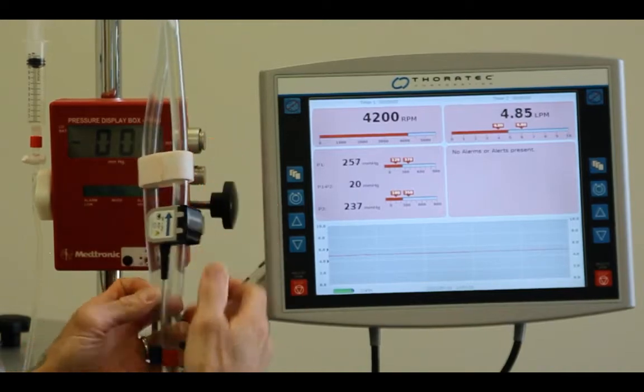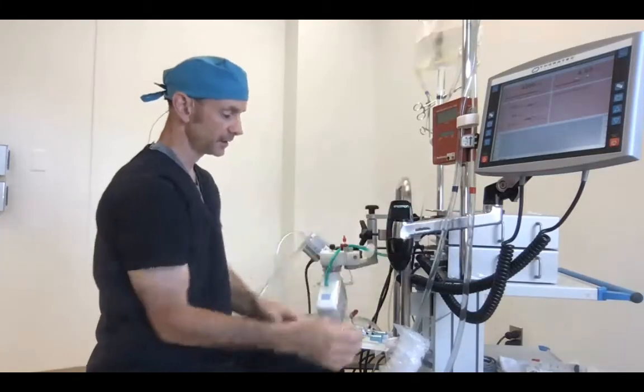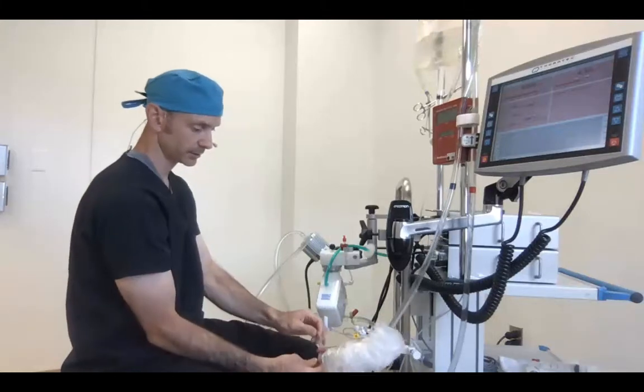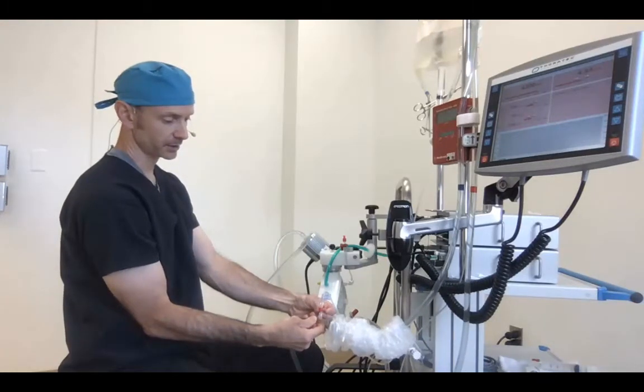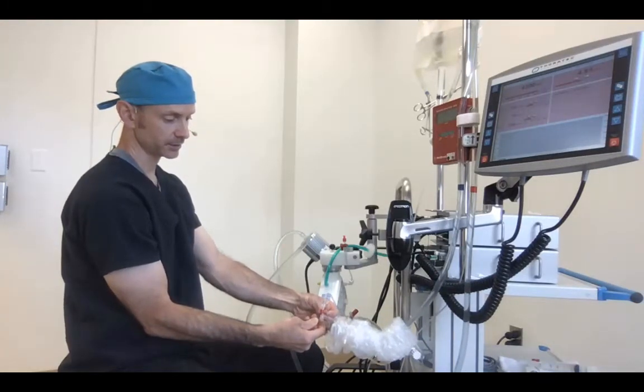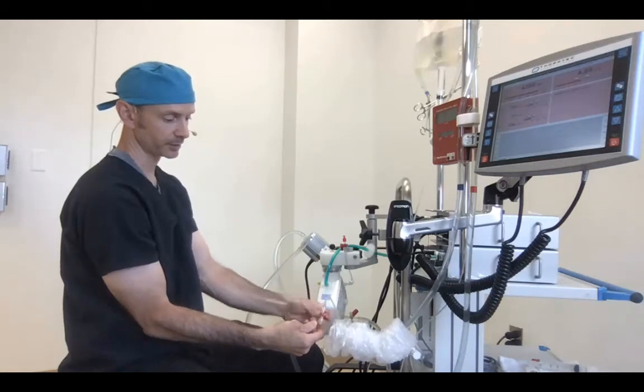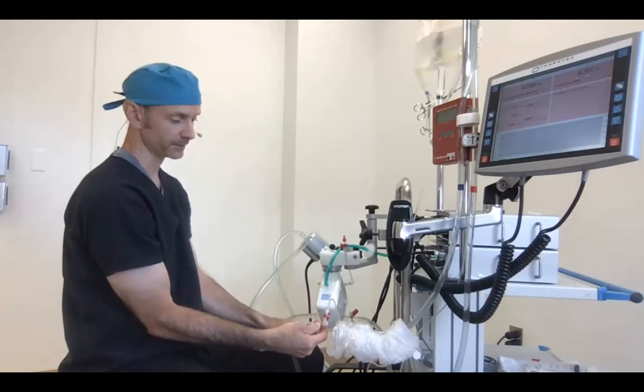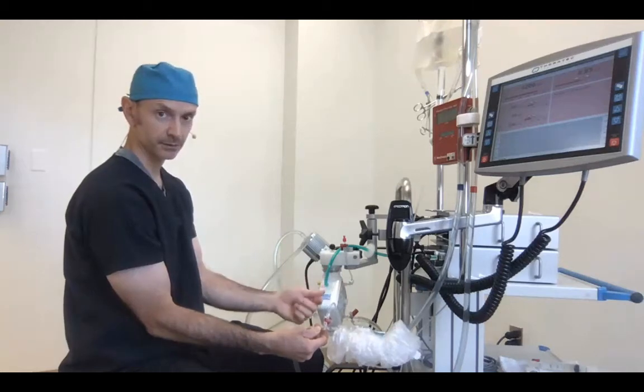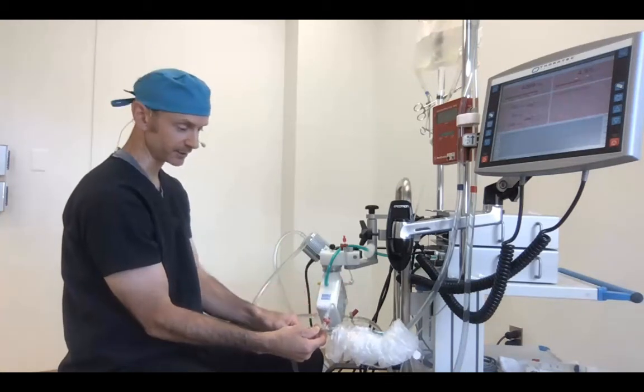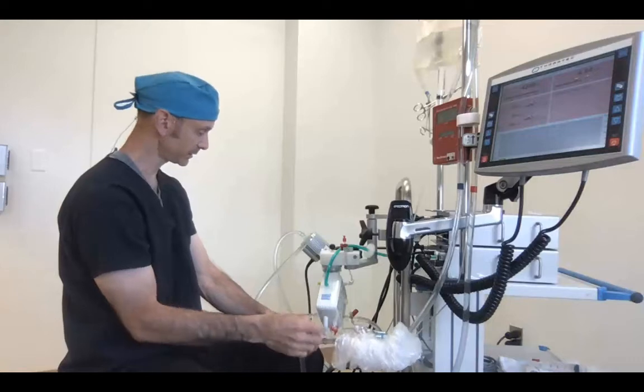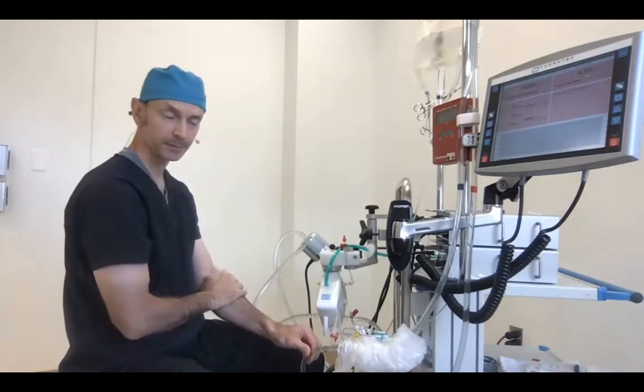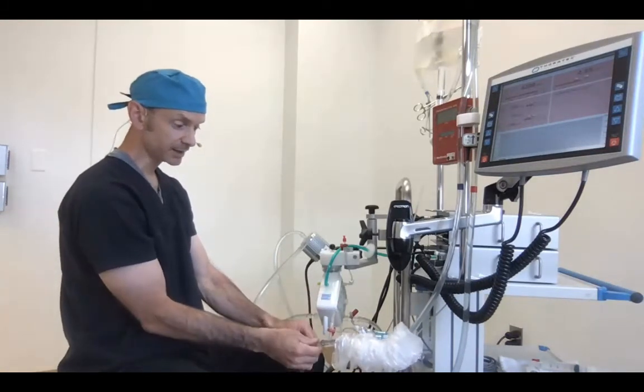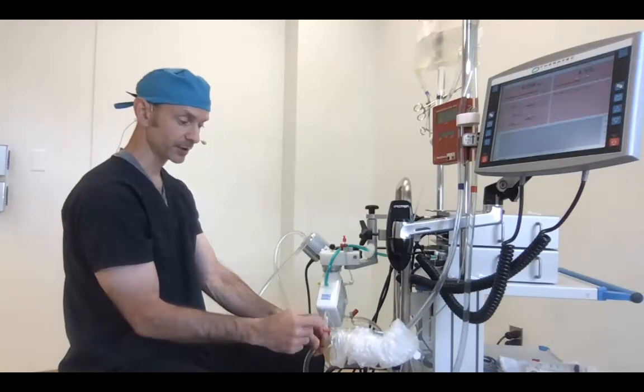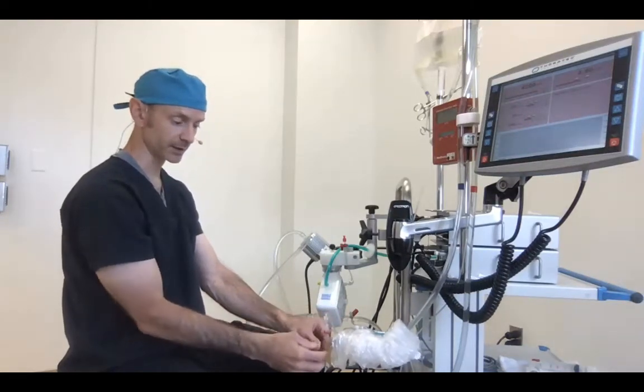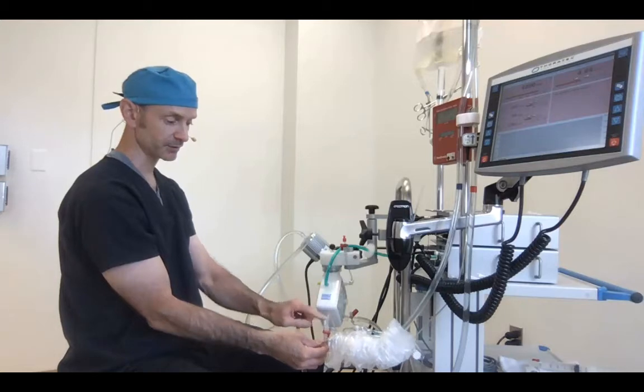Try and not bump that knob because it's always active. And then we'll come back down here and turn this stopcock so that it's off to air and open continuous with the circuit, like that. And you saw that bubble jump there. That's one of the reasons we don't mess around with this venous line. That negative pressure just sucked that bubble down in, and I heard it go over there and hit the pump. So if we're really going to do that clinically, we'd probably have to be super careful to put a red cap on that before we did anything moving around, and not open and close this if there's any bubbles in this line.